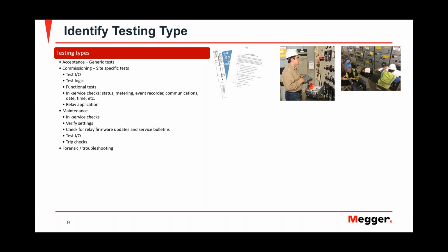You could do forensic or troubleshooting testing. This is when an event has happened and you're checking for the security and the dependability on the relay. So you're making sure that if the relay tripped, you understand why the relay tripped, or if it did not trip and it was supposed to trip, you're trying to understand why it didn't occur. So this is when you go to your event recorder, your data logs, and you try to recreate the event, because maybe that will lead into changing settings or adapting settings or adding settings in order to prevent that anomaly event to happen again.